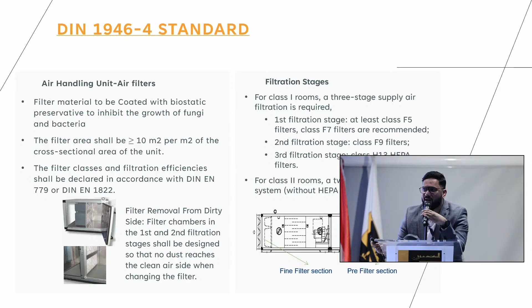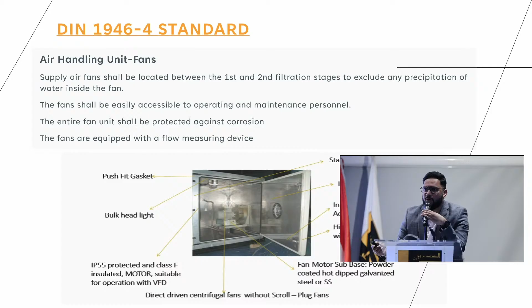Any components used must have a certificate of VDI or minimum VDI or DIN for parts used in the hygienic air handling unit. With the fan section, DIN 1946 standard defines direct driven fans only, you cannot use belt driven fans, whereas VDI standard allows belt driven fans with special coatings. The fan section wiring has to be in stainless steel conduit, with an inspection window and bulk light for maintenance, easily accessible, and should have minimum flow measuring devices to confirm airflow is established, or dampers shut down in case of no airflow.